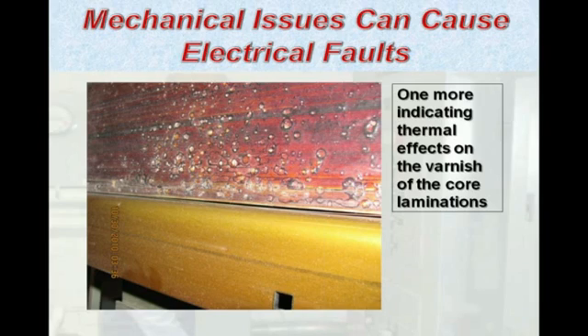And another question here, is it possible to use the ultrasonic probe, or in your experience have you used the ultrasonic probe to pinpoint the mechanical failure location in this case? This got us in the general vicinity, but it leads us to where the faults are by combining all the other testing and technologies to pinpoint it down. The directional nature of the ultrasound makes it good for getting fairly precise, but it doesn't tell us the root cause. In this case, using the airborne and the contact module, we were able to get really precise as to where the emissions were originating from, and verified that once we got the shutdown with the visual inspection, the thermal inspection, and backing it up with the other electrical tests.